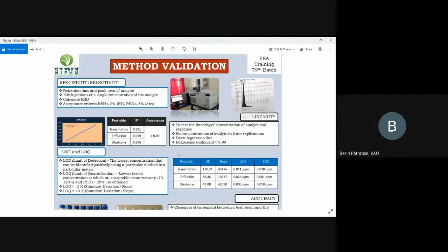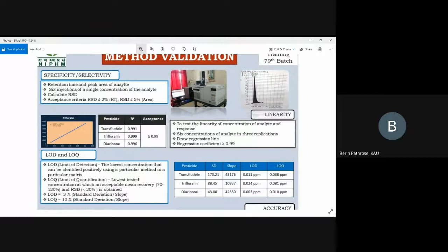Then next, I will explain with this slide. Next is linearity. For linearity, we will prepare 6 concentrations of the standard in 3 replications. You can see it over here, 6 concentrations of the pesticide in 3 replications, and we will inject them. You will get a graph like this, and we will draw the regression equation, and the R square for that should be greater than 0.99. That means as you increase the concentration, the response should also be proportional. It should be linear.